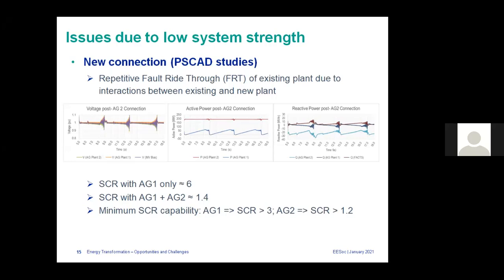So what happens is, if you refer to the voltage plot, you can see at 5 seconds, this is a solar farm. Blue curve is a solar farm. Why is it repeating every 4 to 5 seconds? Why is it repeating in a cycle? Yes, what's happening is if you look at the voltage, around 8 seconds, voltage is very bad. You can see it because of that oscillation. Because when the solar is picking up, system interactions start and voltage is becoming very bad. So then the inverters see this as a problem. So the inverters decide to shut down the solar inverters. So it goes back to 0. You can see around 9 seconds.